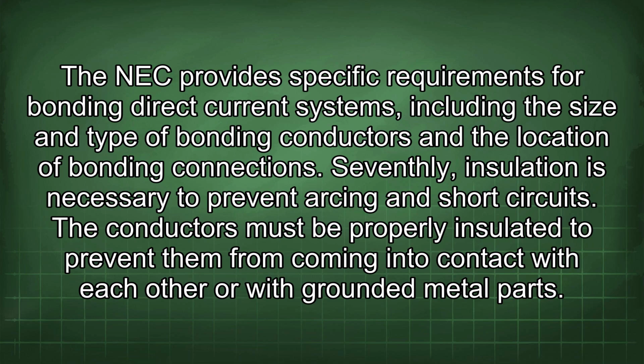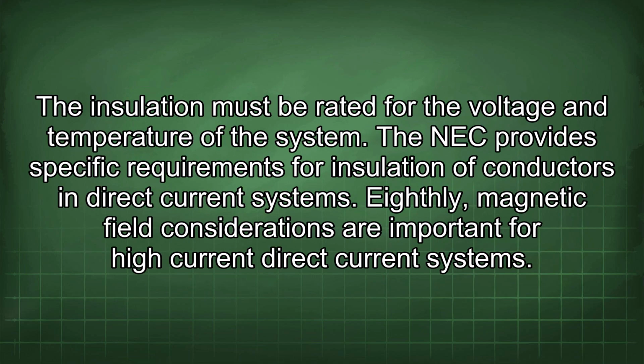location of bonding connections. Seventhly, insulation is necessary to prevent arcing and short circuits. The conductors must be properly insulated to prevent them from coming into contact with each other or with grounded metal parts. The insulation must be rated for the voltage and temperature of the system. The NEC provides specific requirements for insulation of conductors in direct current systems.